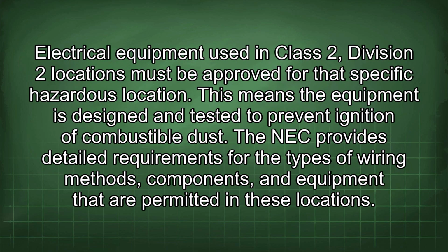Electrical equipment used in Class 2, Division 2 locations must be approved for that specific hazardous location. This means the equipment is designed and tested to prevent ignition of combustible dust. The NEC provides detailed requirements for the types of wiring methods, components, and equipment that are permitted in these locations.